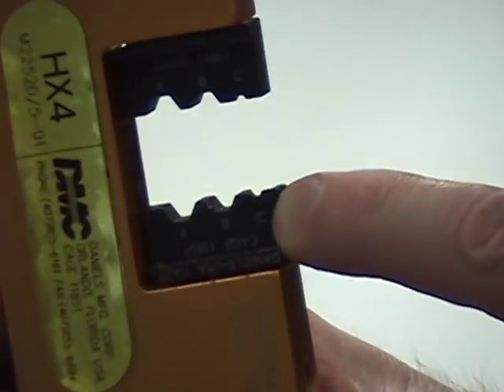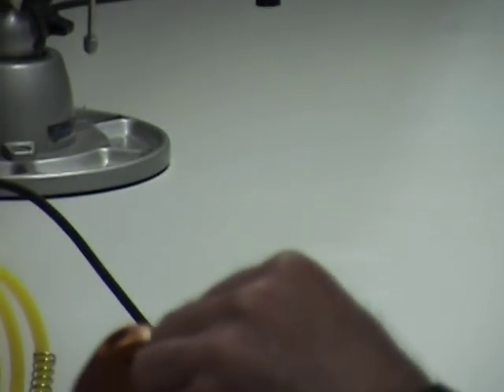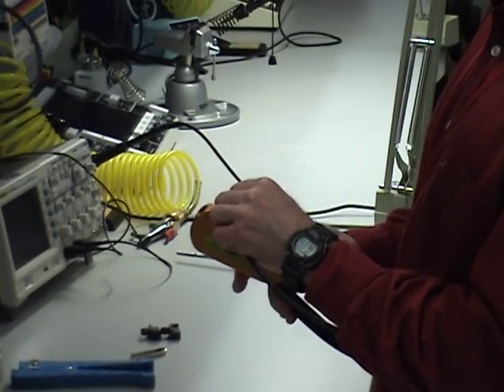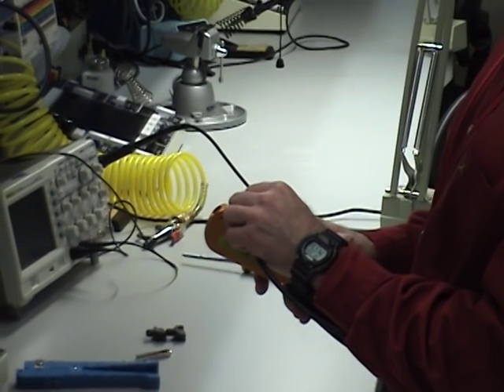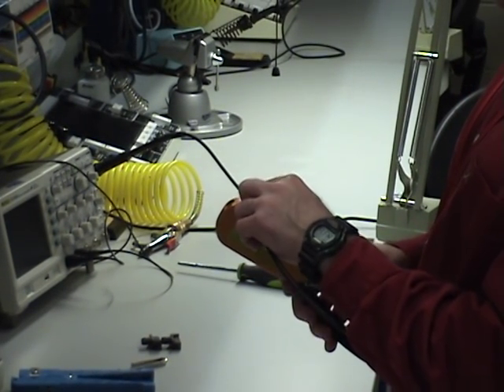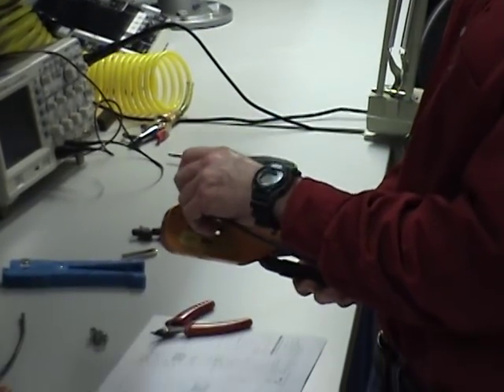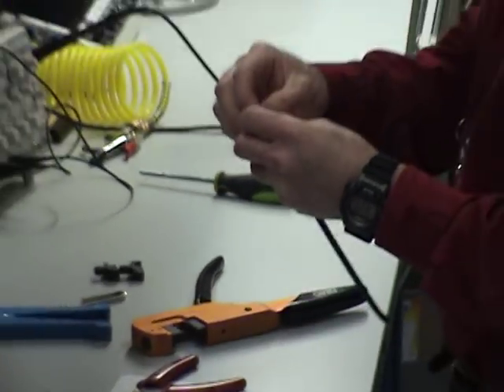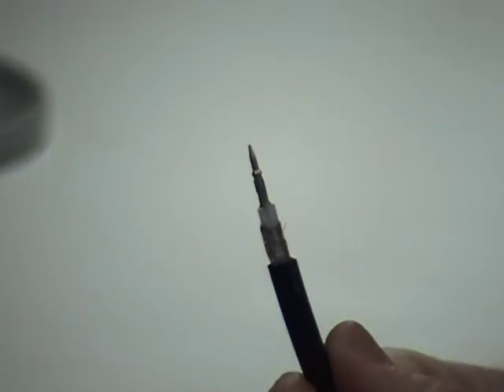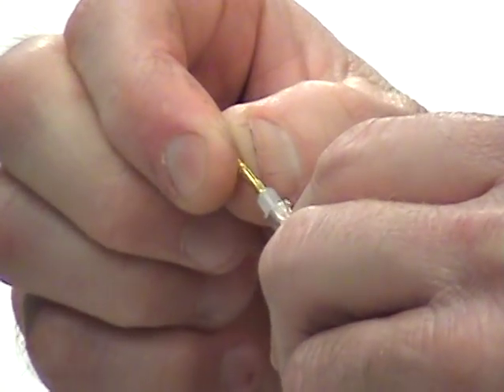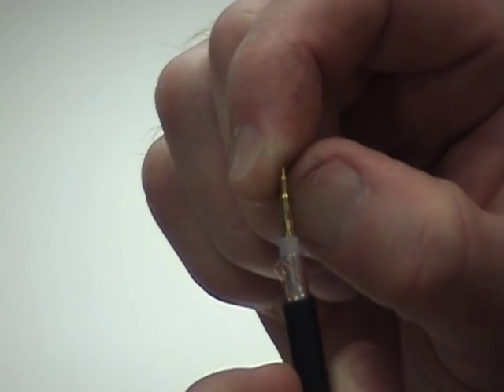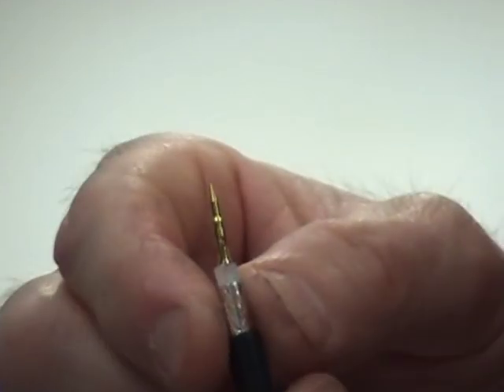I want to be able to look in and it's really only one way to do it. Now it's my inner contact and it said use slot C. So I'm going to use slot C. I'm going to take this contact, place it in the slot, simply crimp it. You want to make sure you're not on the ledge on the side of the dielectric. You crimp it and you take a look. You can see that it's crimped. Give it the tug test and also you look in the inspection hole and make sure that I see the center conductor in the window, which I do. Looks good.